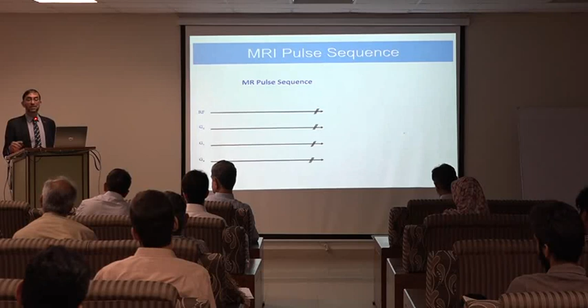So these three gradients, GZ, GY, GX. One is the permanent magnetic field that you applied. Then there are three gradient fields in the x-axis, y-axis and z-axis, and then there is the RF pulse which you applied. So this is the k-space where you want to store data. GZ is known as the slice select gradient. When you say I want to image my knee, that slice select gradient will choose the particular value suitable for the knee, so that its resonance frequency is maintained. It's all programmed inside the MR scanner.